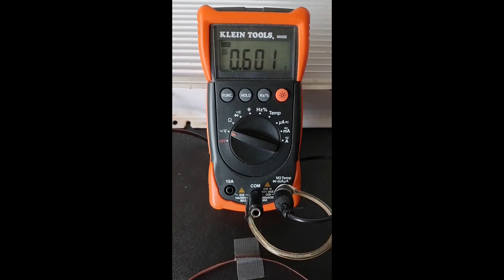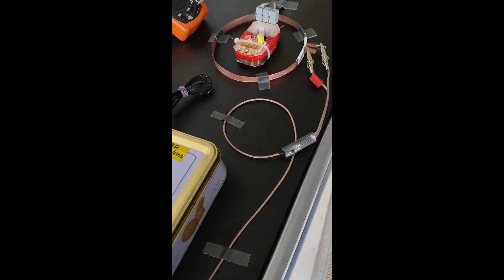Except for a small gap at the terminals, this copper strap loop almost encloses the time-varying magnetic field produced by the current in the energized coil. The test leads connected to the open terminals of the loop convey the induced loop EMF to the AC to DC converter input.